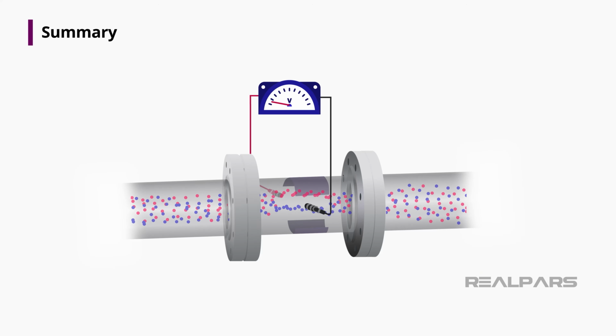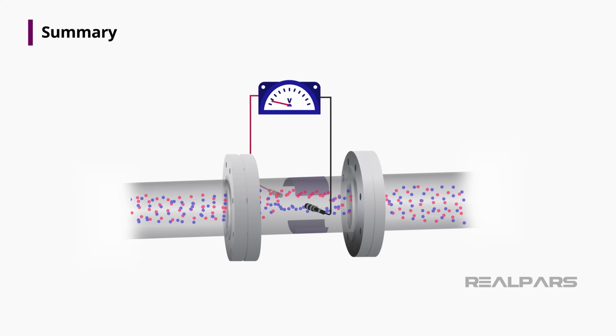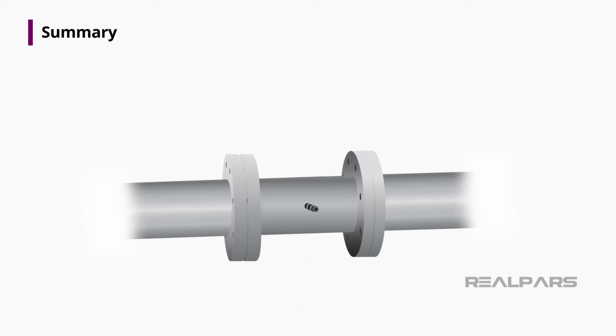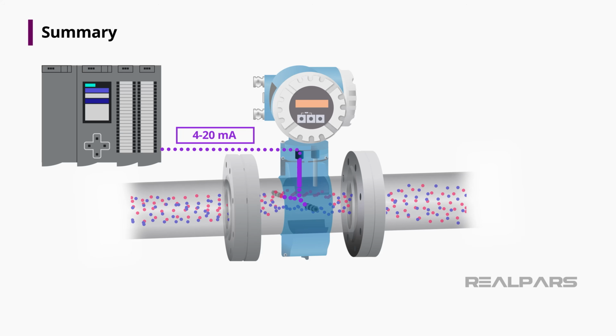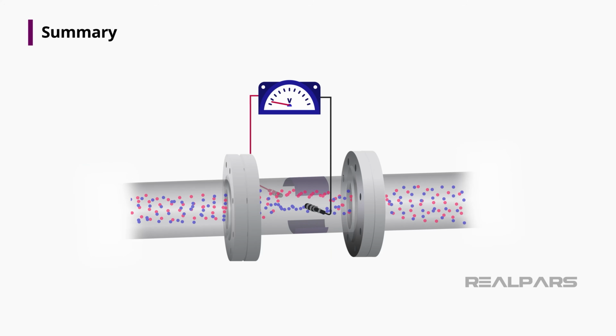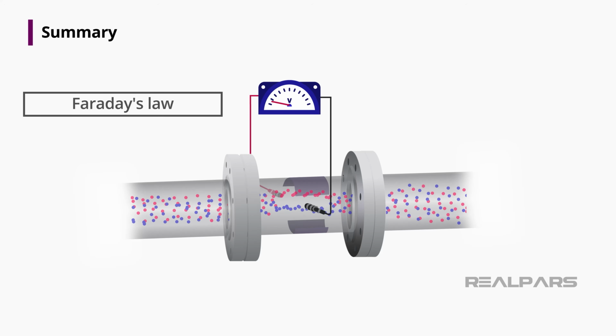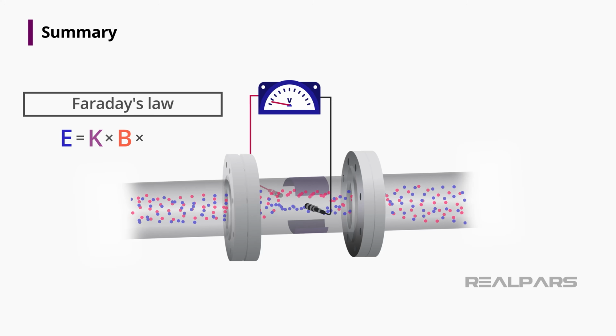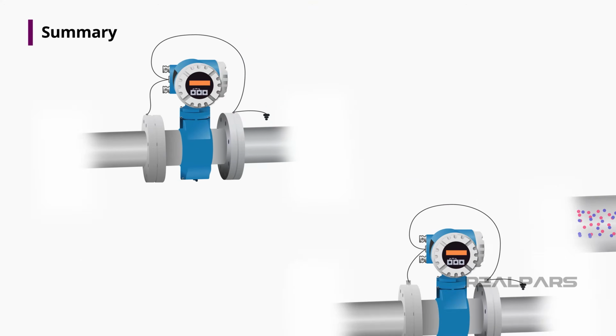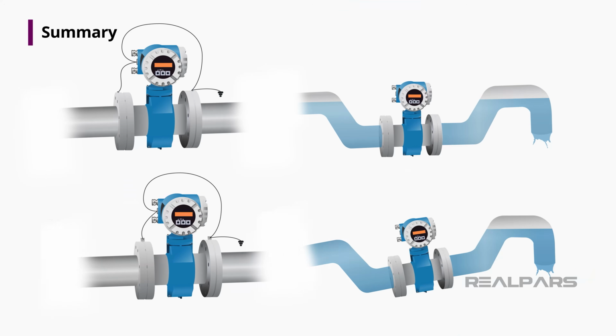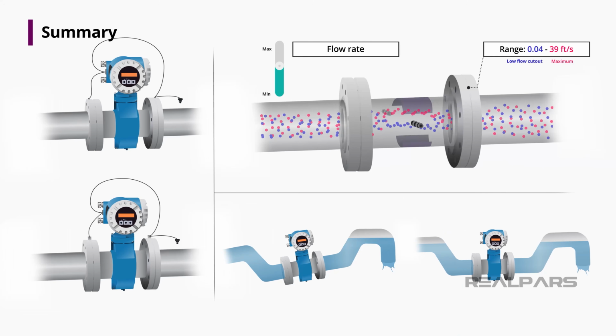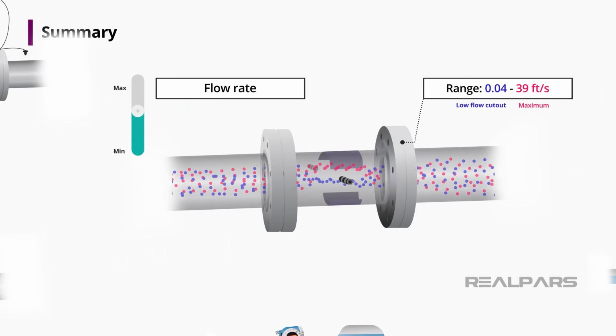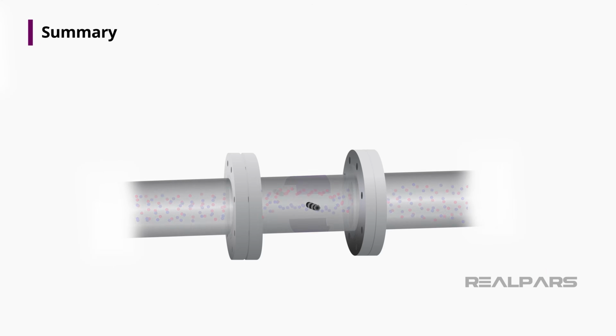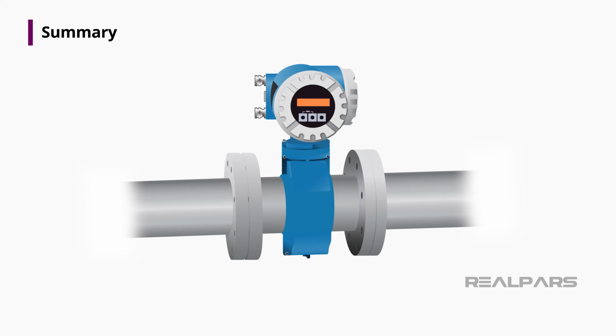In this video, I introduced you to the working principles of the magnetic flow sensor, its physical properties, and how mag meters are used in industrial measurement and control systems. I demonstrated the linear relationship between the velocity of the flowing fluid and the electrical signal, developed based on Faraday's law. Using proper grounding techniques, selecting the best location for installation, and understanding the minimum and maximum flow limits for the meter will help ensure accurate flow measurement. So the next time you see a magnetic flow meter installed in a plant, you'll have a much better understanding of how this simple yet sophisticated sensor measures flow.